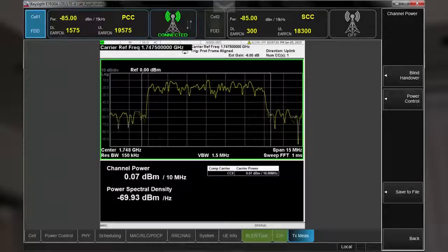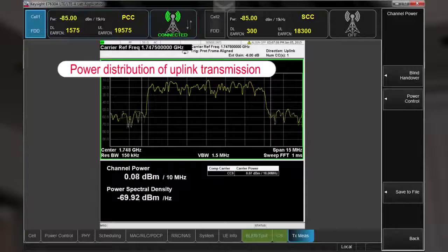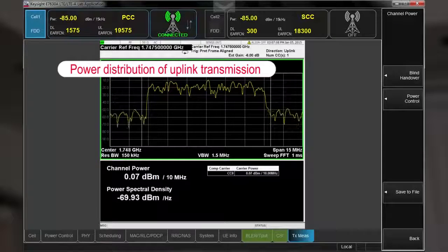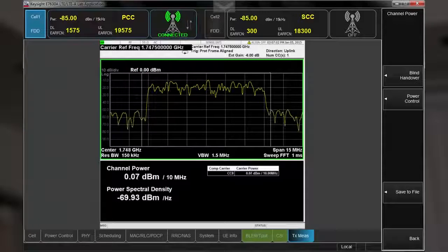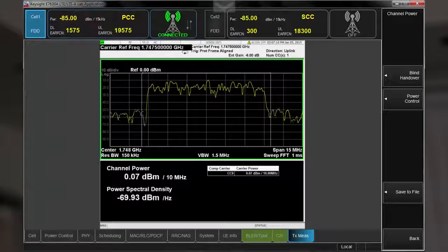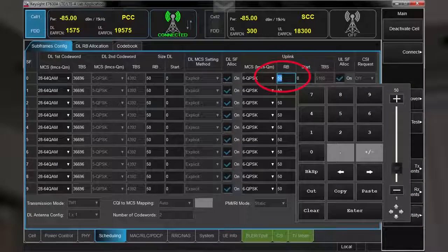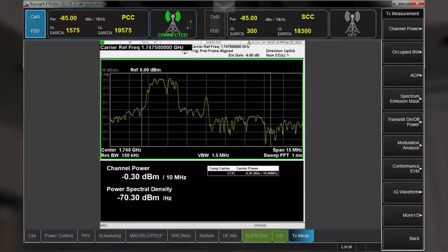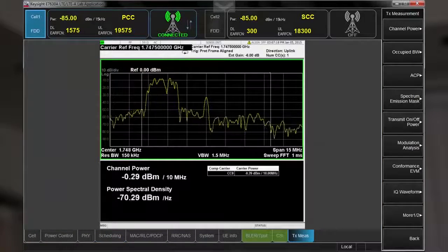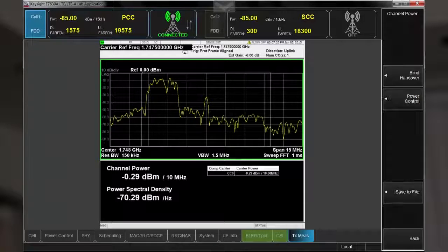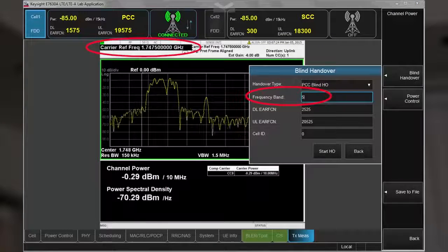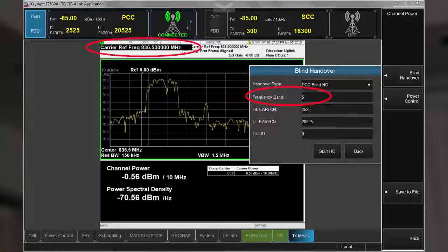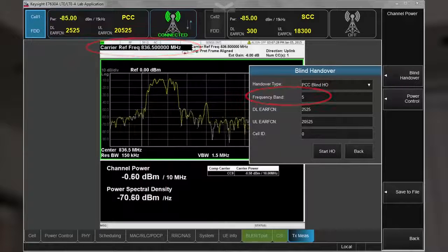We'll start with channel power. Here you can see the power distribution of the uplink transmission. Using the UXM's flexible uplink and downlink channel configuration capabilities, I'll change to a partial allocation of 12 resource blocks. Here you can see the resulting change in the transmit power profile. We can also easily hand over to a new band and channel to perform testing over various frequencies.